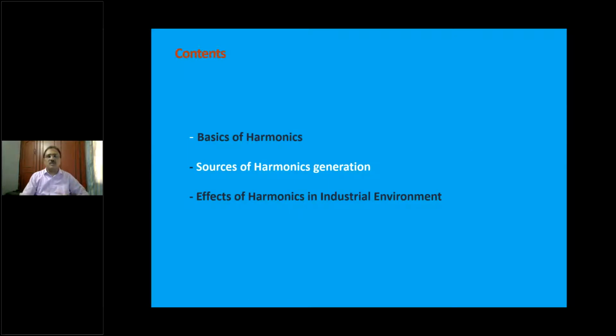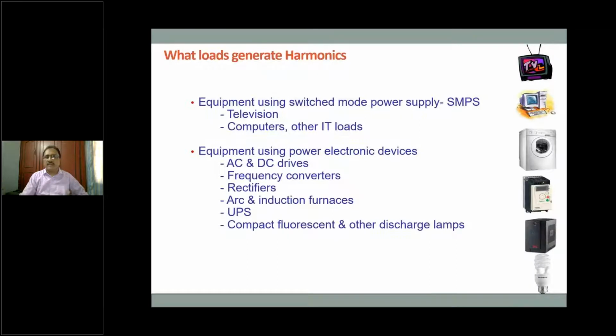What are all those loads which generate harmonics? We'll take a look. For each I have only about 4 slides, so don't fear. It will be simple and you will be able to appreciate it. Equipment using switched mode power supply, SMPS, like televisions, computers, and other IT loads are generators of harmonics, particularly third order harmonic, because they are single phase loads.